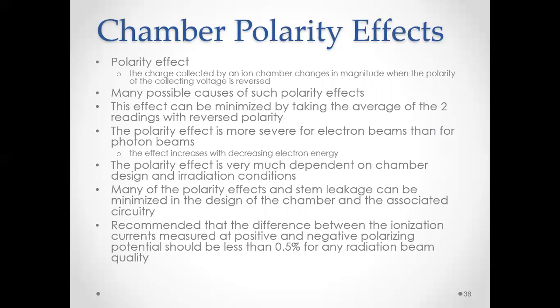The polarity effect refers to a change in the magnitude of charge collected when the polarity of the collecting voltage is reversed. It can be minimized by averaging readings at two reverse polarities. The effect is more severe for electron beams than photon beams and increases with decreasing electron energy. It is very dependent on chamber design and irradiation conditions. The recommended standard is that the difference between ionization currents at positive and negative polarizing potentials should be less than 0.5% for any radiation beam quality.